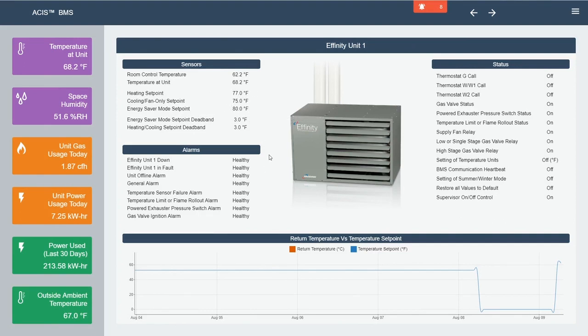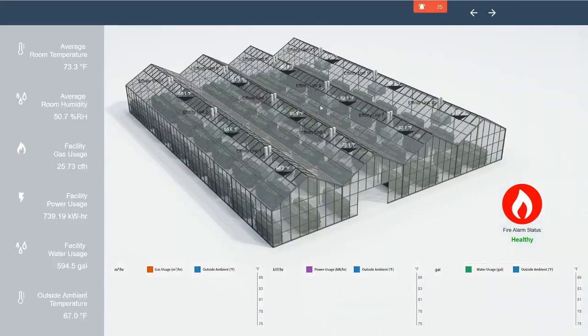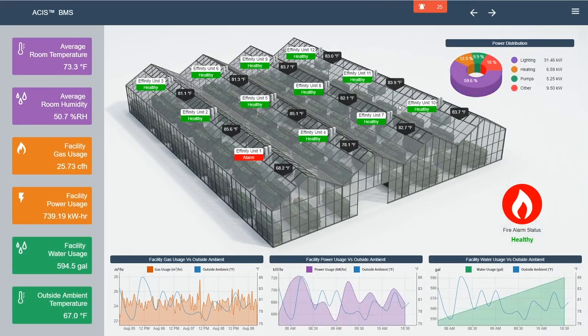One of the big things for the customer is he gets alarm statuses back from the unit. Instead of having to watch the temperature in the space and say, okay, the temperature has dropped by 10 degrees or 15 degrees, whatever he's got that set at, now he can have actual alarm feedback in real time from the unit. So I just generated an alarm on this unit, which is now showing here as a temperature limit or flame rollout alarm, which is obviously great for the customer because as soon as he gets a problem, he knows. And if you go back to the overview, you can see Effinity Unit 1 is in alarm.